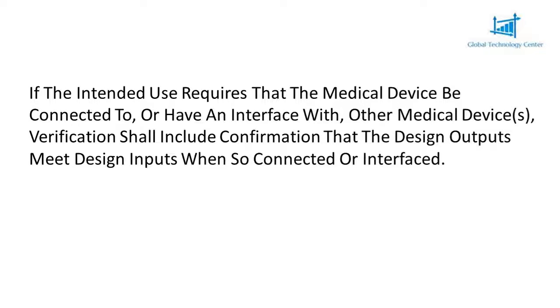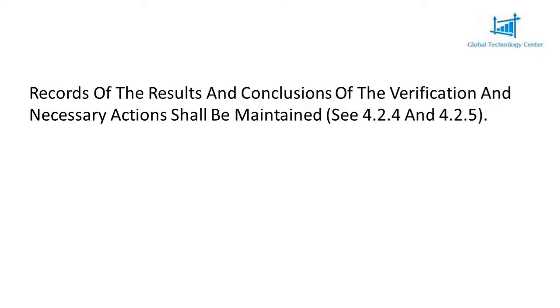If the intended use requires that the medical device be connected to, or have an interface with, other medical devices, verification shall include confirmation that the design outputs meet design inputs when so connected or interfaced. Records of the results and conclusions of the verification and necessary actions shall be maintained.